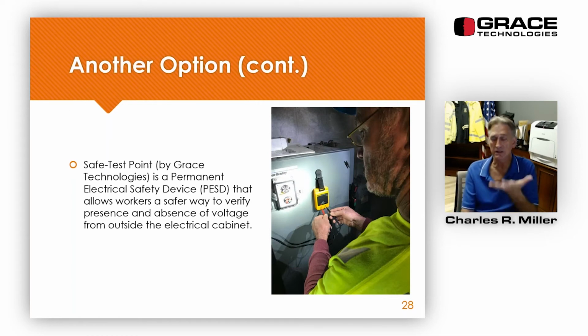They also have impedance built in, so even if you were to touch the blades of the meter, and I've seen this done where they put a paper clip in from one to the other, it did not short it out because of the built-in impedance. So what this guy did, he tested the meter, tested for the absence of voltage, tested the meter again, and the cabinet could be opened at that time without wearing shock and arc-rated PPE.